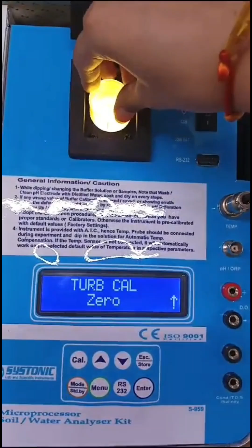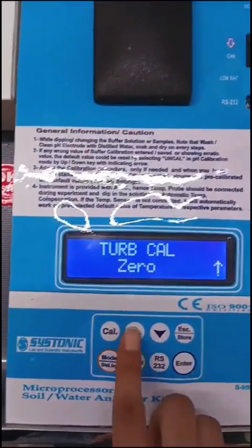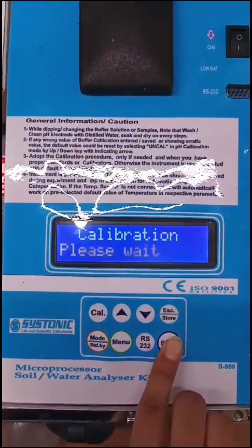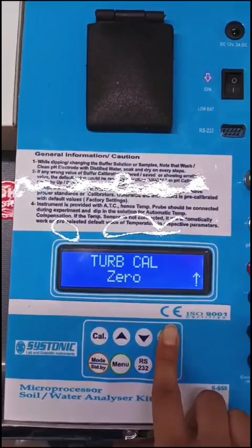Now we will put the standard solution test tube inside the holder. Make sure you shake the test tube vigorously. After that, put this inside it and go to calibration and then press enter. As my solution is 400 NTU, I will go to 400 and then press enter. You can also make solutions of 200, 100 and 400 NTU by the instructions given in the manual, and the process for them will be the same. After that, go to escape and then to mode, and from here you can see the value.